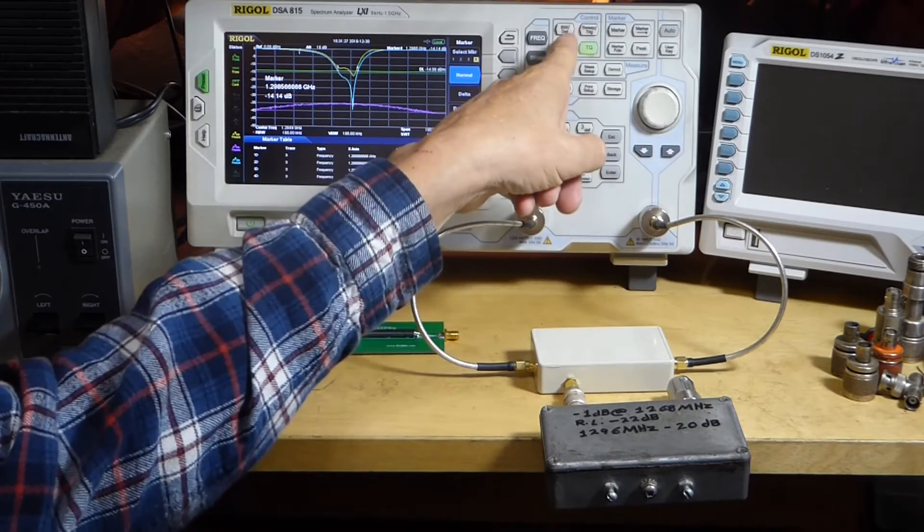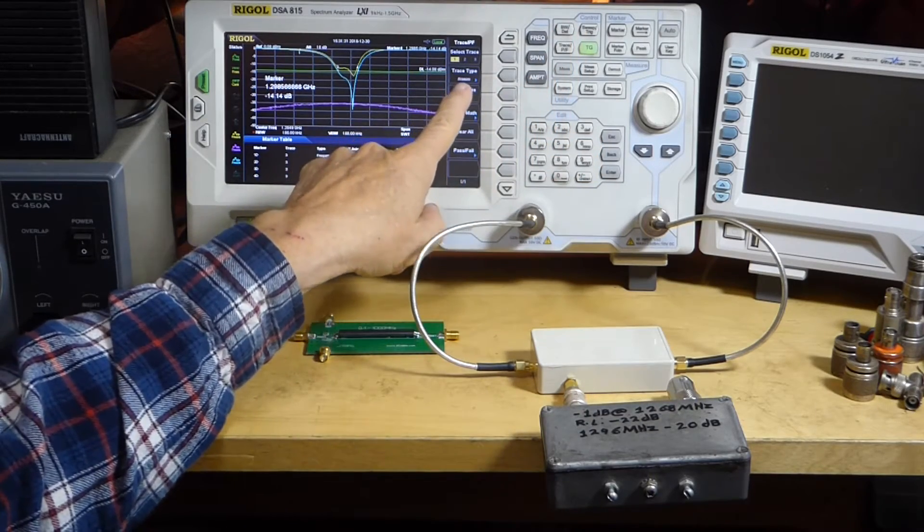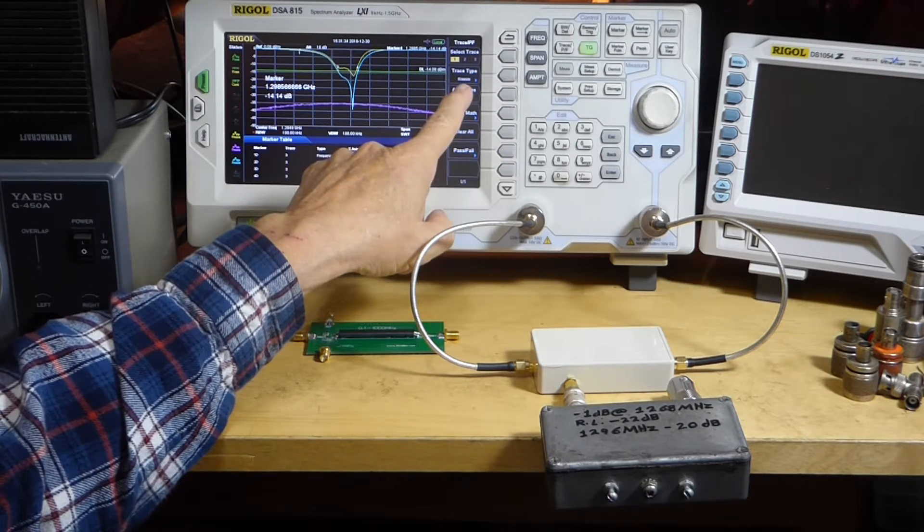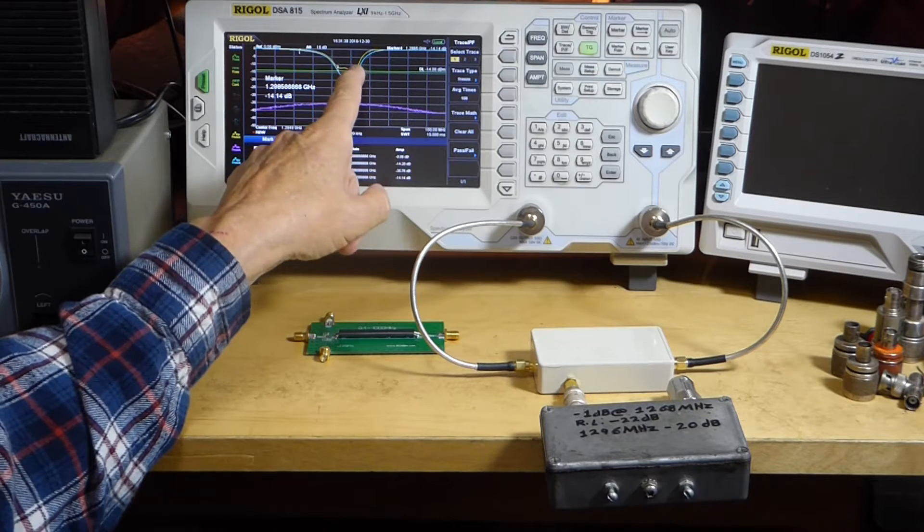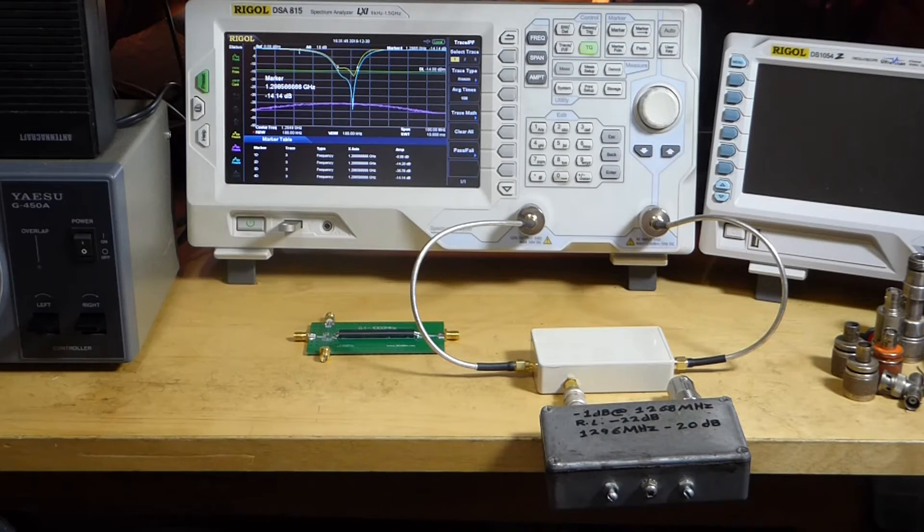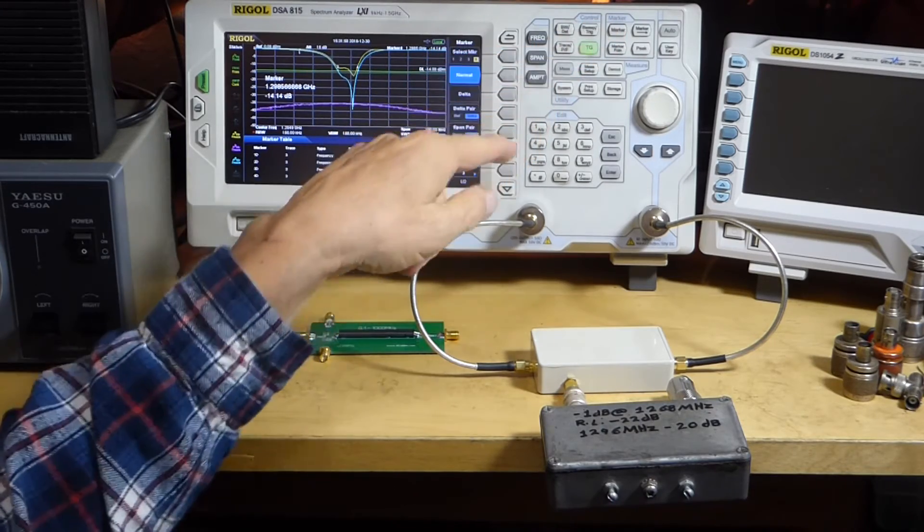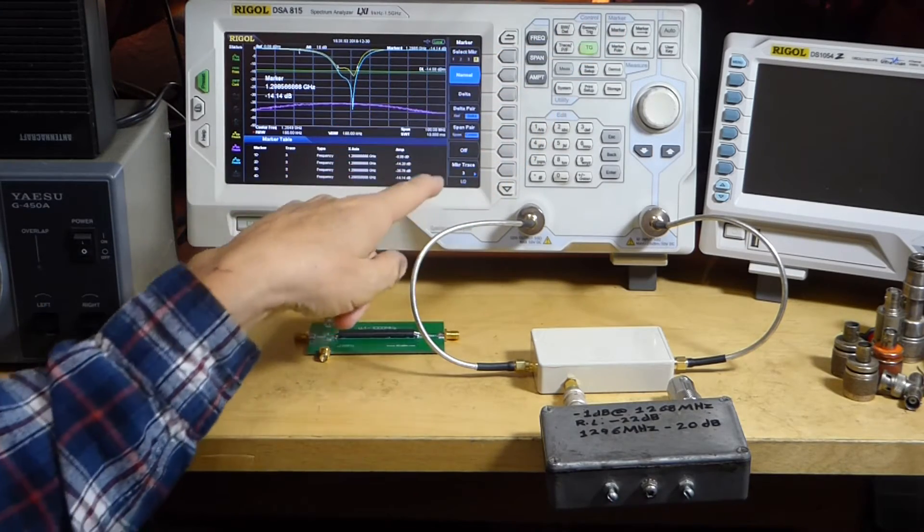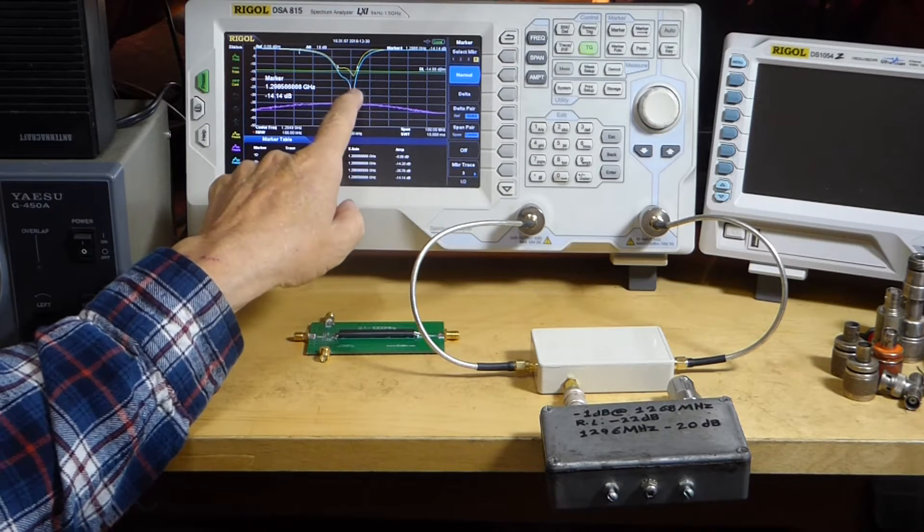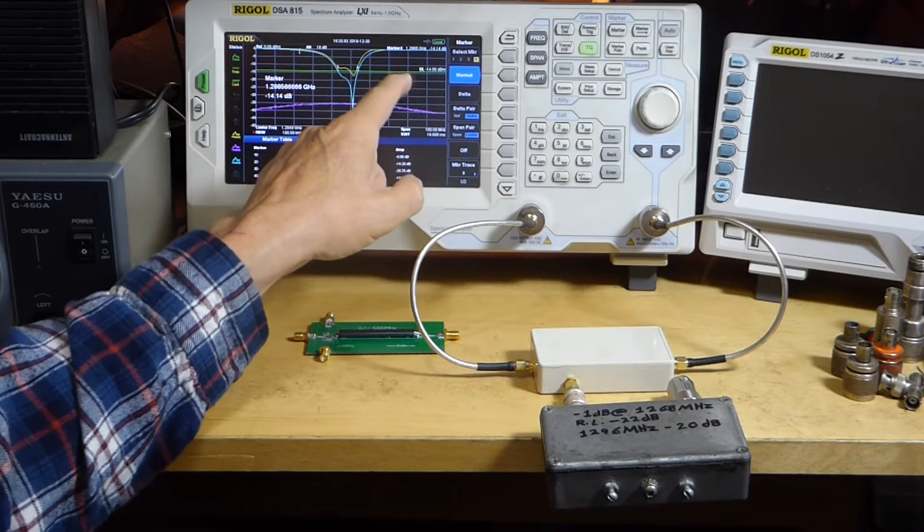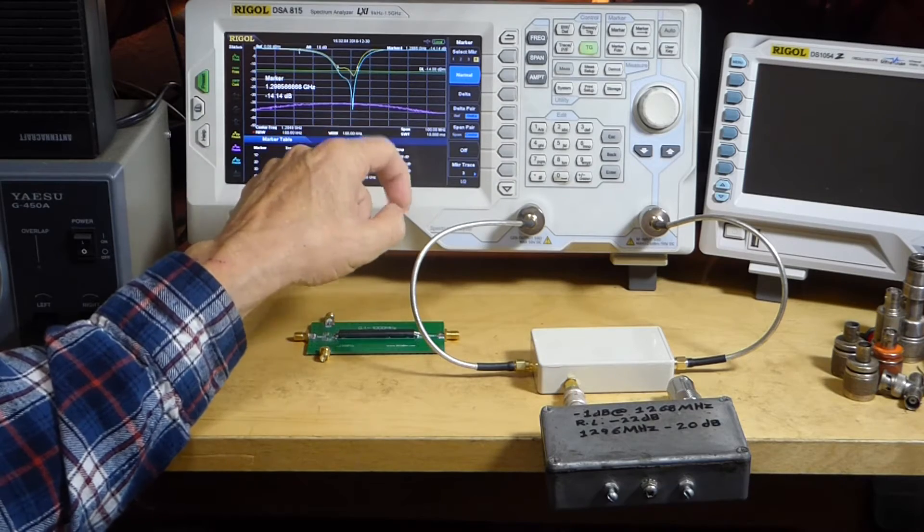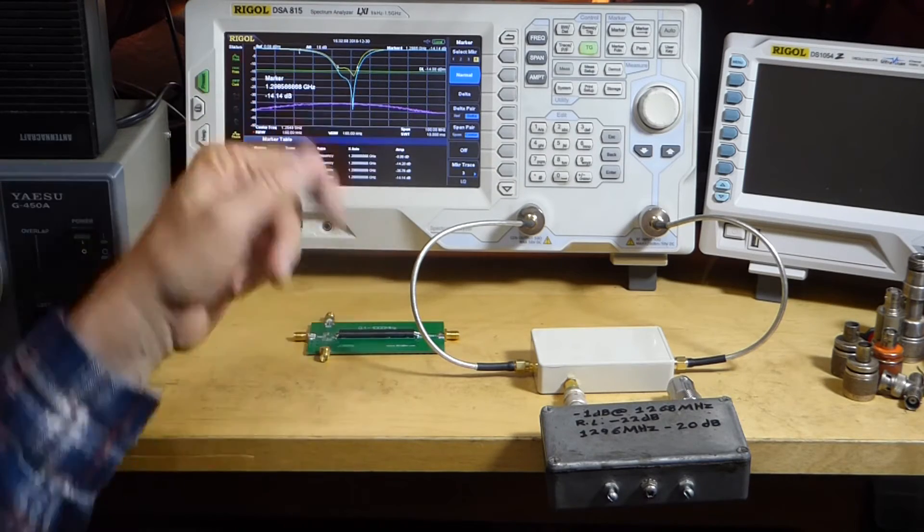So if I go to trace 1 here, you'll see it's frozen. And if I go to 2 or 3, they'll also be frozen. And so that's been saved separately and calibrated separately for each test. And so they're all on the screen at one time here. Like marker 4 is from trace 3. This is trace 3, the blue trace. And so all of those are on trace 3. I could have put them on 2, which is the yellow, or I could have put them down here.